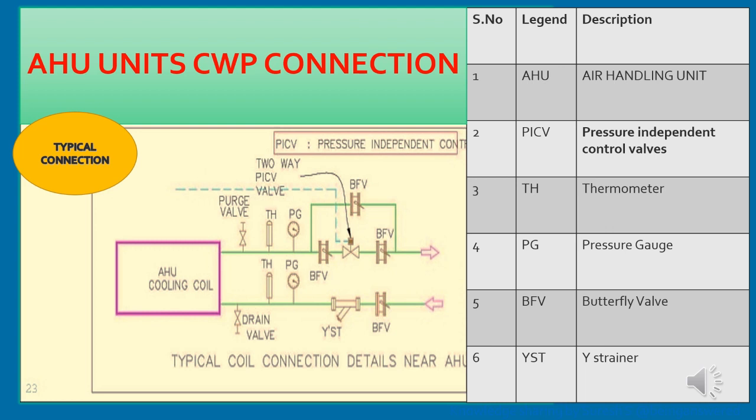Now we are going to see how a typical AHU chilled water pipe connection works. AHU is the air handling unit. PICV is a pressure independent control valve, TH is a thermometer, PG is a pressure gauge, BFV is a butterfly valve, and YST is the strainer. The strainer always has to be installed in the supply line towards the AHU.